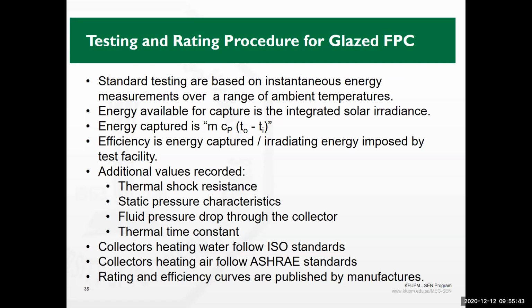the test facility. And tests are not necessarily done in real solar energy operation, because waiting for a day of clear sky and days with different temperatures is not easy. So what they do is try to mimic everything in the lab by having special lamps that resemble the solar energy, and they have their labs at controlled conditions in terms of weather, air conditioning in the lab, temperature of the air, and even the temperature of the water in and out of the collector.